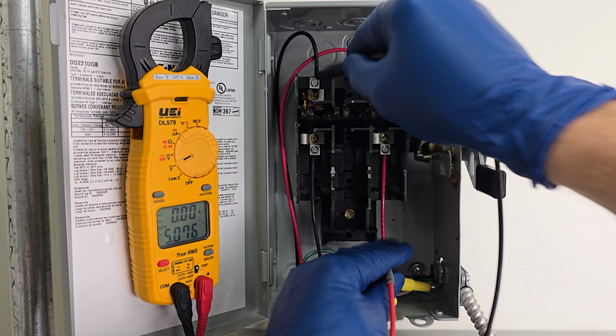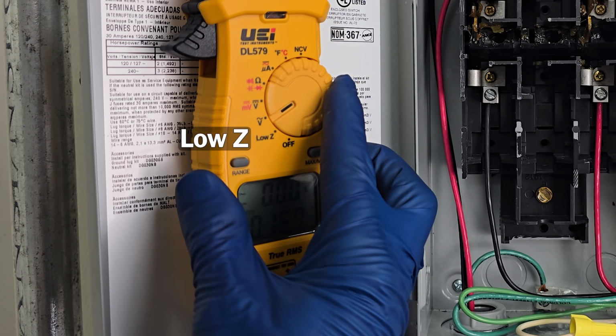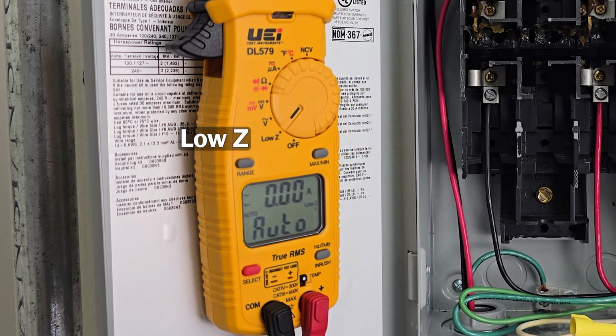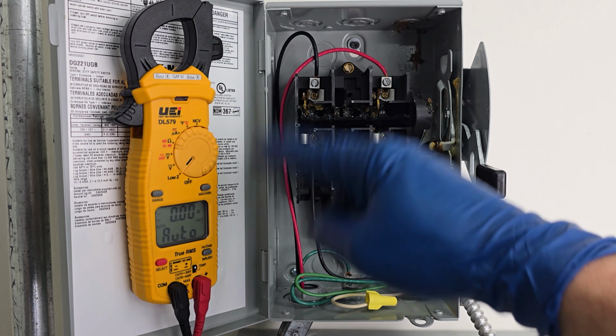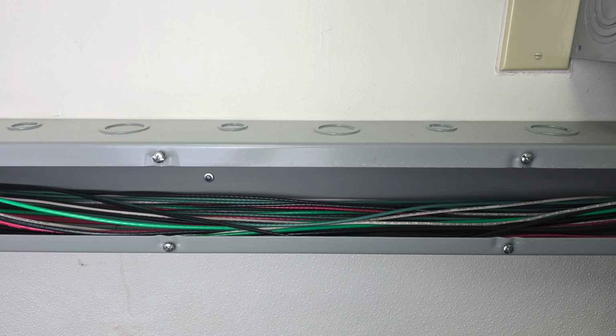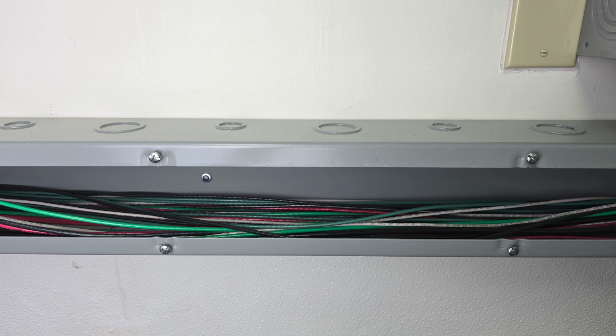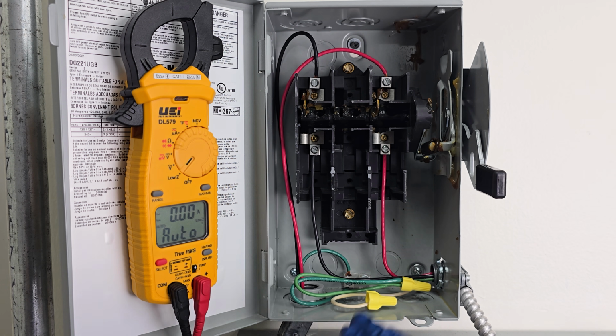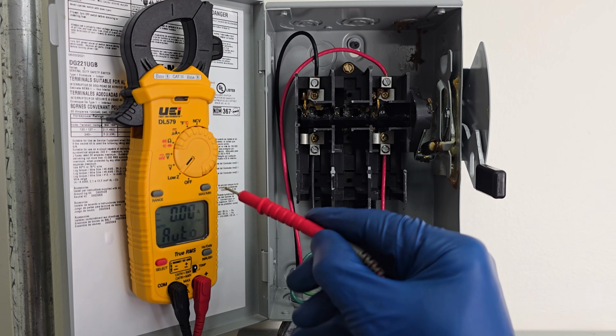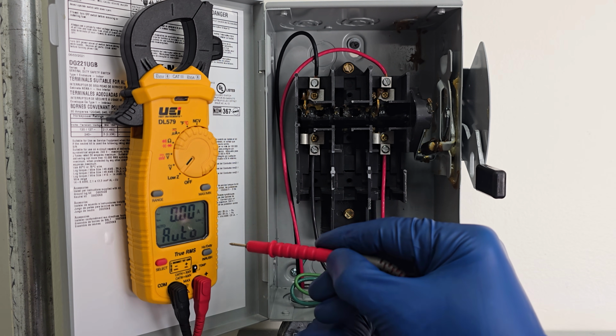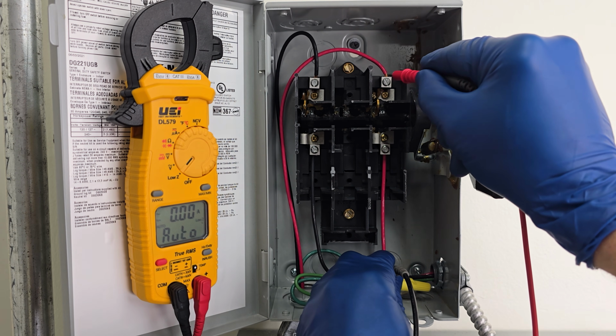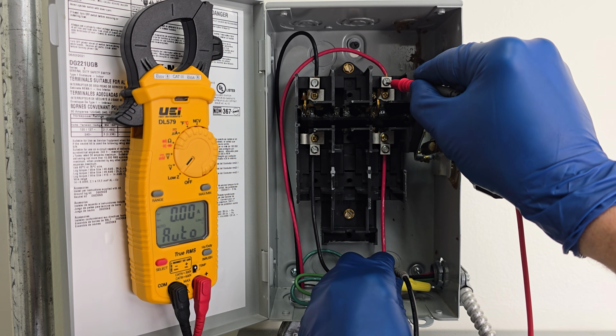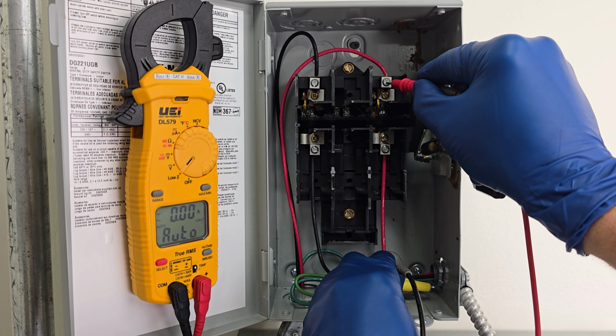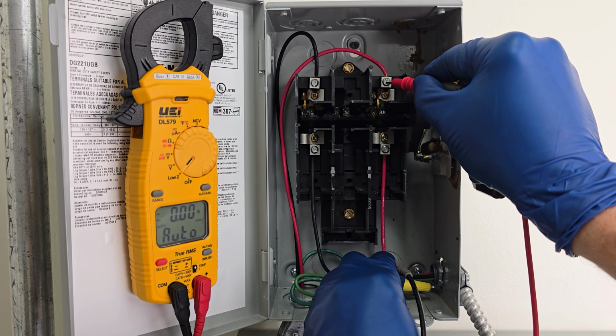And to show you that, what we can do is we can switch over to the low Z. So that means low impedance. And what's happening is these wires are traveling through a wire trough next to some other wires, and current is being induced into these wires, even though they're off at the main panel, and it's showing a ghost voltage. So what's happening here is the multimeter is adding extra resistance, is actually adding a little bit of a load to get rid of the false ghost voltage. And so that 5 volts is not actually really there. It's not being supplied with 5 volts or 7 volts.